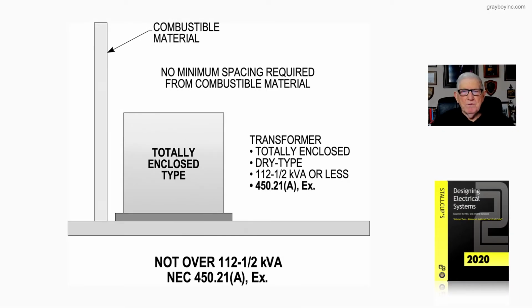Now let's review figure 20-24. We're going to deal with transformers not over 112.5 kVA in accordance with NEC 450.21a, exception. Notice we have combustible material in the illustration, and the transformer is totally enclosed, dry type, with or without ventilating openings. We're installing it in accordance with 450.21a and the exception.